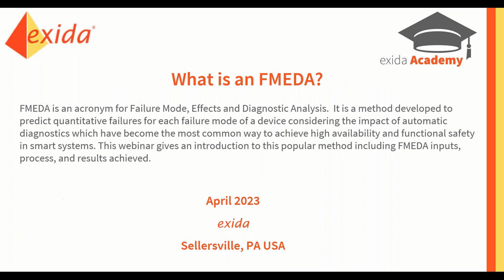So yeah, let's get straight into it. What is an FMEDA? FMEDA is an acronym for failure mode effect and diagnostic analysis. It was a method developed to predict quantitative failures for each failure mode of a device, and the key element added to this type of analysis was the impact of automatic diagnostics. We'll work through this as the webinar progresses.